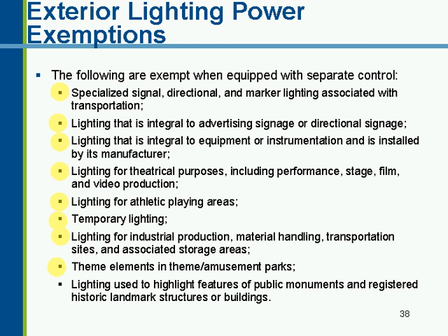Theme elements and theme amusement parks. And again, similar rule as casino gaming areas. If it's part of the theme element, it can be exempted, but standard lighting, back-of-house operations, other general area lighting would have to be counted. And again, lighting used for public monuments, historic landmarks, etc., that is exempted as well.